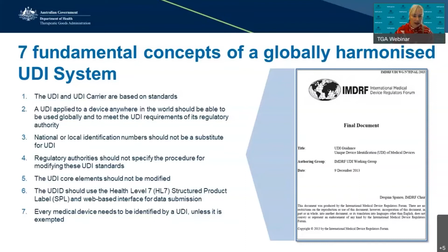There could be national or local identification numbers in place, but that should not be a substitute for the UDI. Regulatory authorities should not specify the procedure for modifying these UDI standards. And the UDI core element should not be modified either, because that brings inconsistency and some confusion into the system. There's also some concepts around the labelling and types of interface for data submissions, and every medical device should be identified by a UDI unless it is exempt, and we might talk a little bit about that later on.